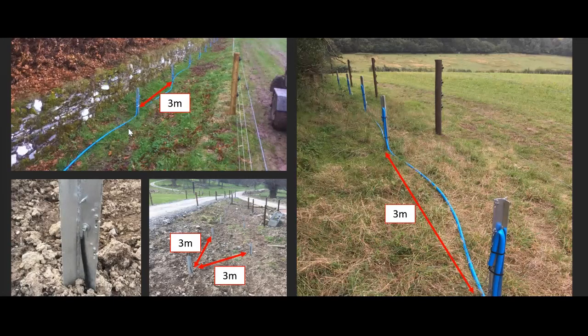Scaffold tubing can also work really well, as long as it's highly galvanized and strong enough to be driven in to depth. The Clipex, or wide profile posts, in these pictures have been driven to a depth of 1.5 to 1.8 meters, being 2 meters long themselves, and they've been driven in 3 meters apart. That's really a key part of an effective earthing system.